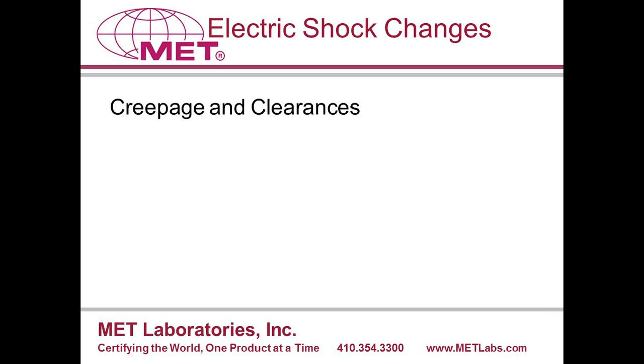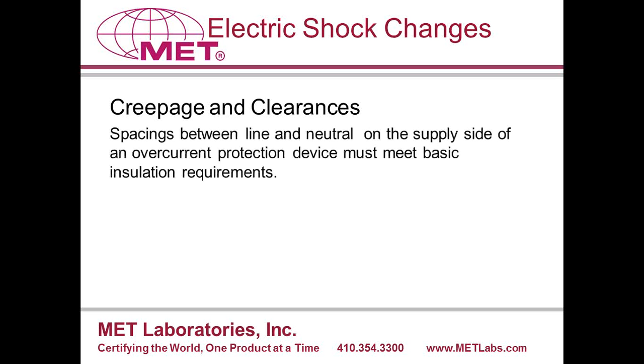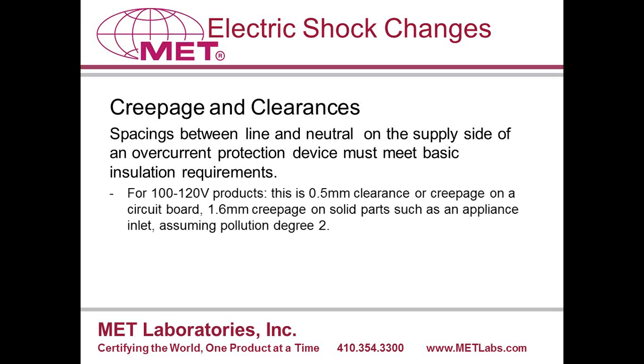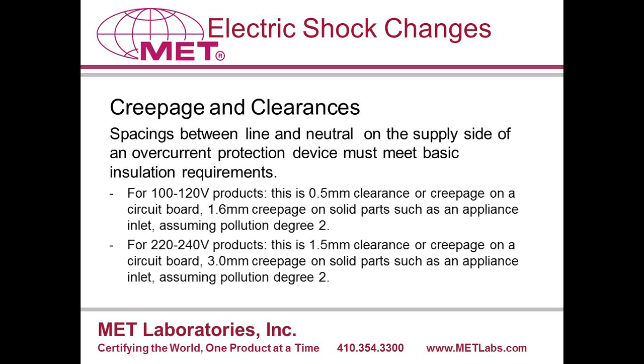One more change to creepage and clearance. There is now a required spacing between line and neutral on the supply side of an overcurrent protective device based on basic insulation. The values are based on North American and European products and are given here.